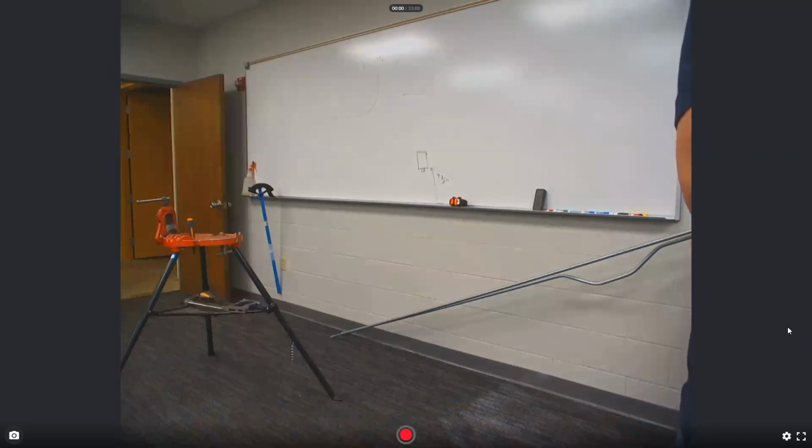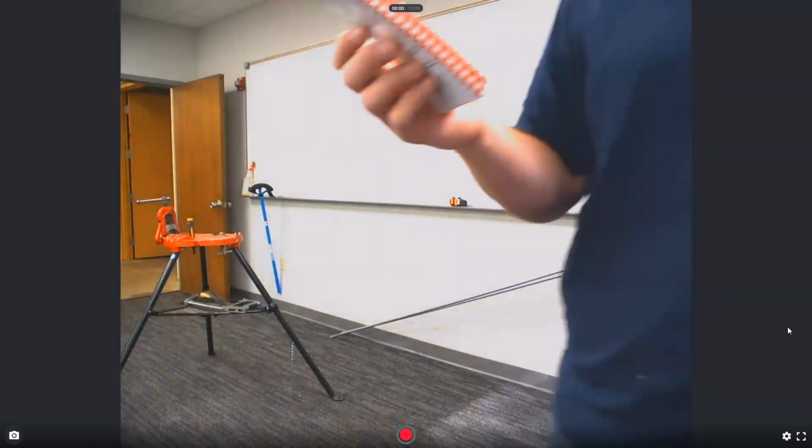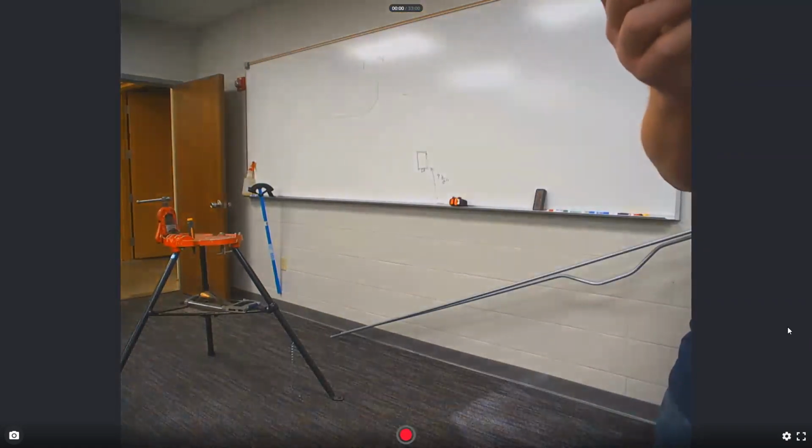But it even shows you which mark to put on there. So 1/2 inch EMT, the take up is 5 inches, 3/4 inch is 6 inches, 1 inch EMT is 8 inches, and 1 1/4 EMT is 11 inches. Everybody see that?